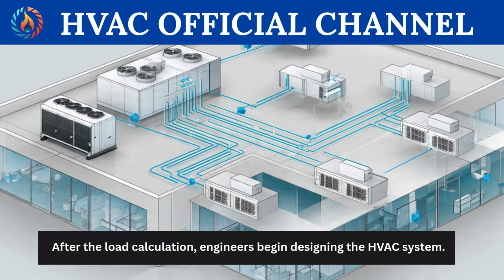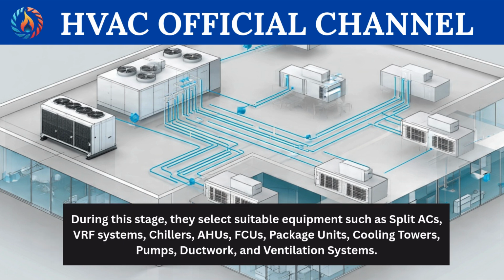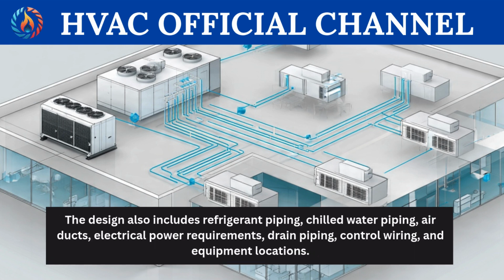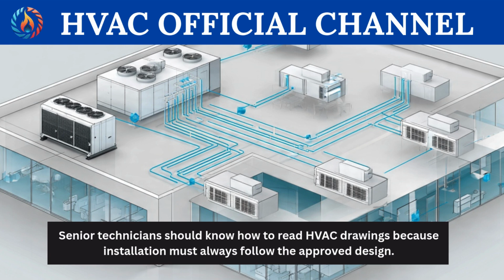HVAC system design. After the load calculation, engineers begin designing the HVAC system. During this stage, they select suitable equipment such as split ACs, VRF systems, chillers, AHUs, FCUs, package units, cooling towers, pumps, ductwork, and ventilation systems. The design also includes refrigerant piping, chilled water piping, air ducts, electrical power requirements, drain piping, control wiring, and equipment locations. Senior technicians should know how to read HVAC drawings because installation must always follow the approved design.